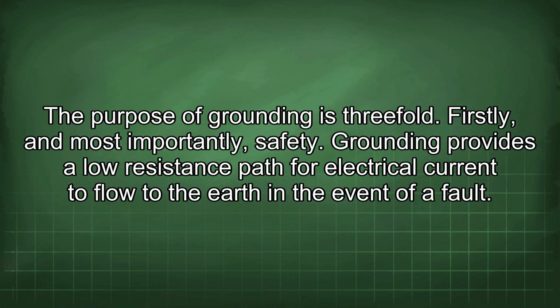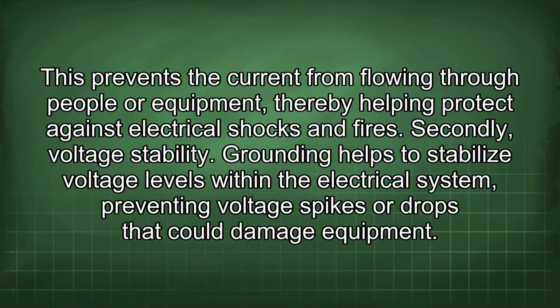The purpose of grounding is threefold. Firstly, and most importantly, safety. Grounding provides a low resistance path for electrical current to flow to the earth in the event of a fault. This prevents the current from flowing through people or equipment, thereby helping protect against electrical shocks and fires.